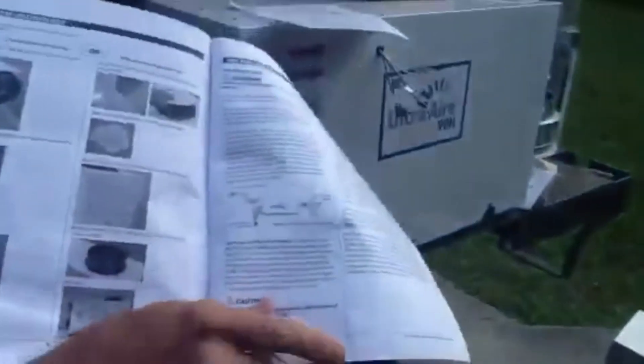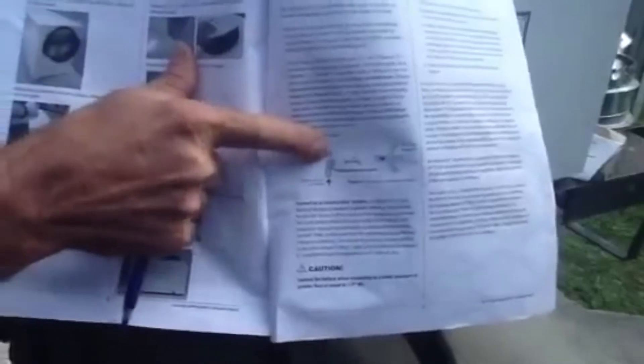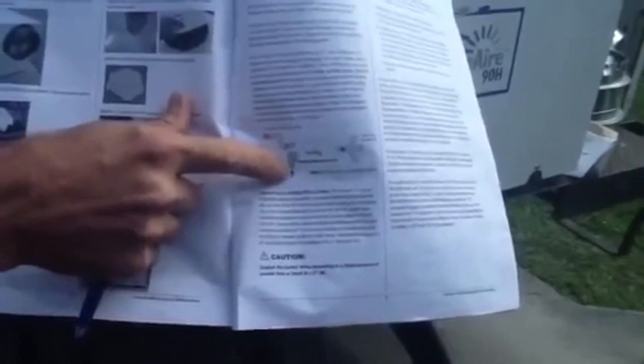Basically, what we're going to do here is we're going to use this particular formula right here. We're going to bring in a 10 inch flex from the main return off the air handler. Then we're going to come off with another 10 inch piece of flex, and we're going to come off with two pieces of eight.